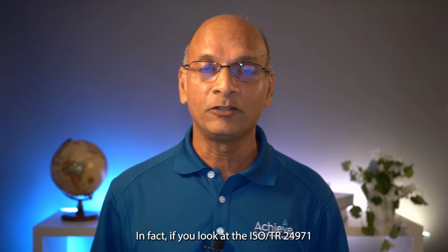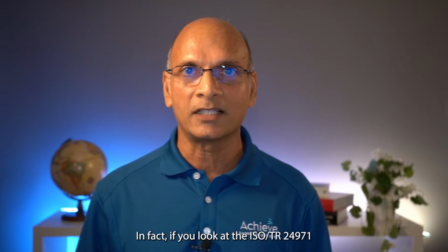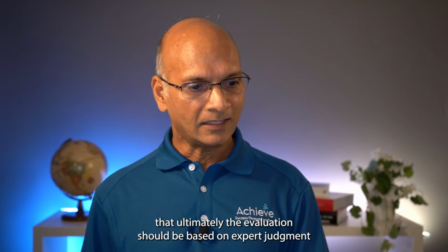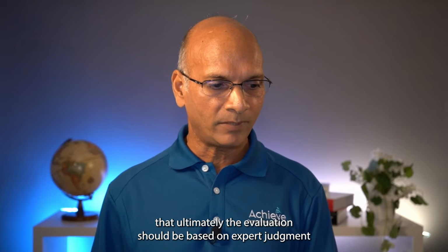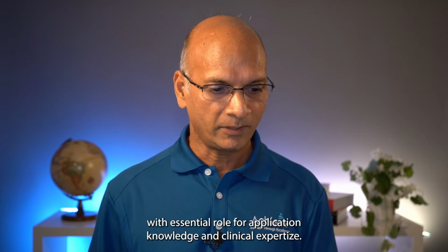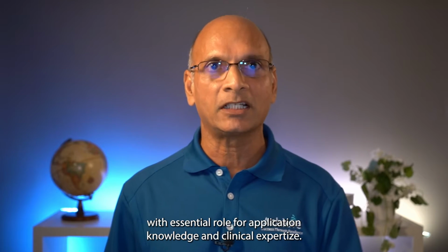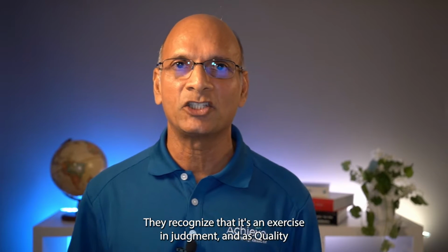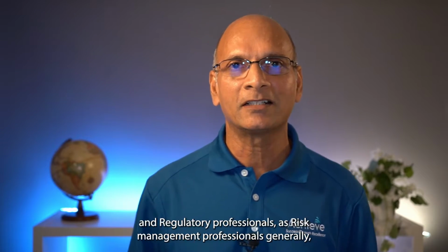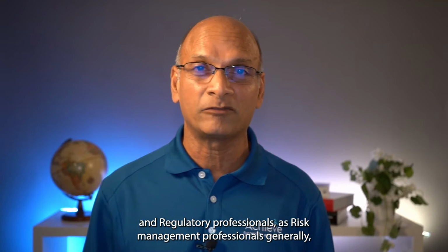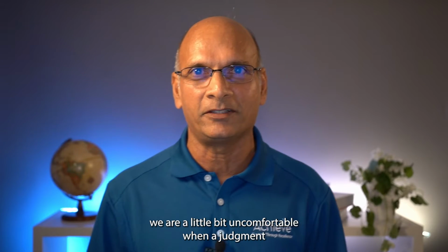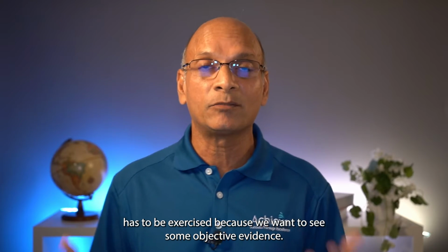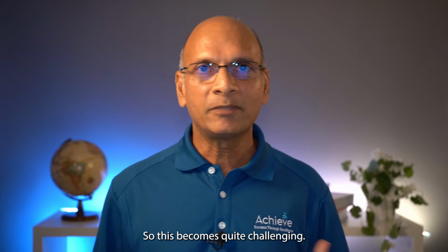In fact, if you look at the ISO TR 24971 guidance, they make a statement that ultimately the evaluation should be based on expert judgment with essential roles for application knowledge and clinical expertise. They recognize that it's an exercise in judgment. And as quality and regulatory professionals, as risk management professionals, generally we are a little bit uncomfortable when a judgment has to be exercised because we want to see some objective evidence. So this becomes quite challenging.